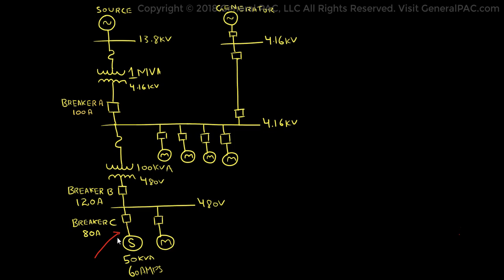Let us consider a three phase fault of 20,000 amps occurring at the load terminals beyond breaker C. Under normal operating conditions, we would require breaker C to trip first. If the breakers used a definite time characteristic, breaker C would have a delay time of 0.30 seconds for a 20,000 amp fault. This means that the high fault current remains on the circuit for at least 0.30 seconds, then breaker C will trip to isolate the fault.